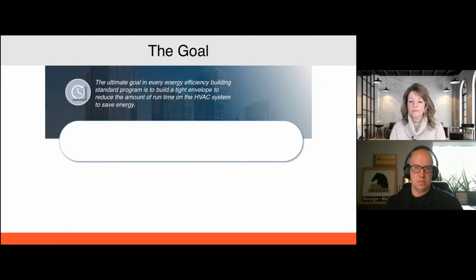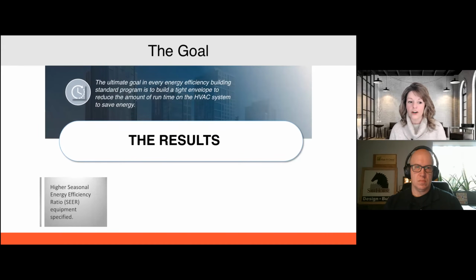So the ultimate goal in every energy efficiency building standard program is to build a tight envelope to reduce the amount of runtime on the HVAC system to save money. That's the goal. The result is we're using higher energy efficiency ratio equipment, seasonal energy efficiency ratio equipment, so higher SEER equipment. We've got ductless mini splits out there that are 30 plus SEER, which is great for energy efficiency. But the challenge is that they can't remove the moisture by focusing on the energy efficiency to get to that temperature.